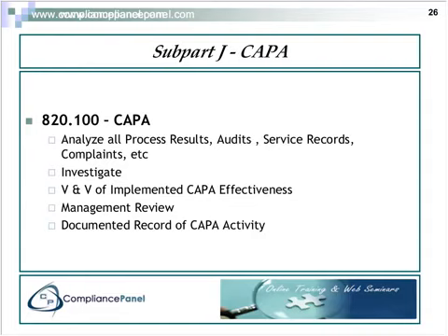This is an area which is normally omitted as part of people's quality system. They implement the corrective action, they implement the preventive action, but they don't go back and see that it was properly effective to correct the situation. The CAPA system provides us with a vehicle for continuous improvement of the product and processes, and inputs and outputs from the CAPA system are forwarded all the way up the ladder to executive management to be used during their periodic management review of the quality management system.